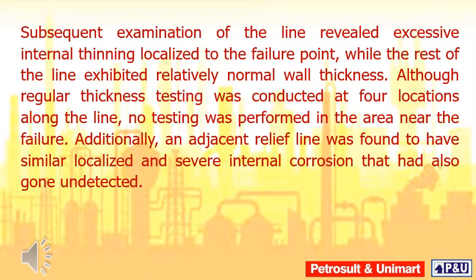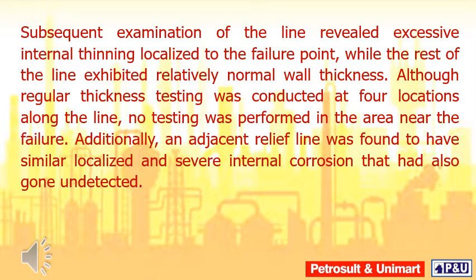Subsequent examination of the line revealed excessive internal thinning localized to the failure point, while the rest of the line exhibited relatively normal wall thickness. Although regular thickness testing was conducted at four locations along the line, no testing was performed in the area near the failure. Additionally, an adjacent relief line was found to have similar localized and severe internal corrosion that had also gone undetected.